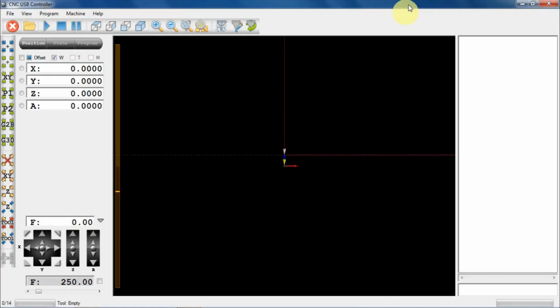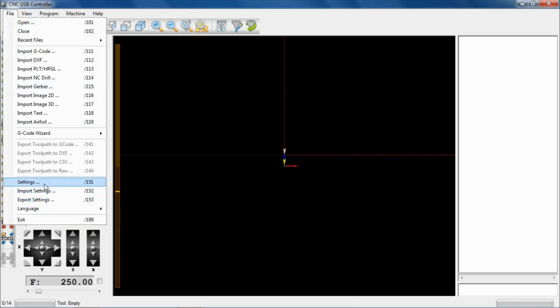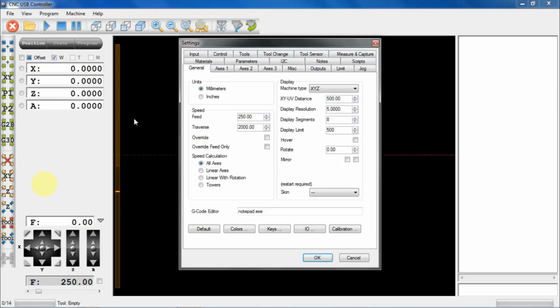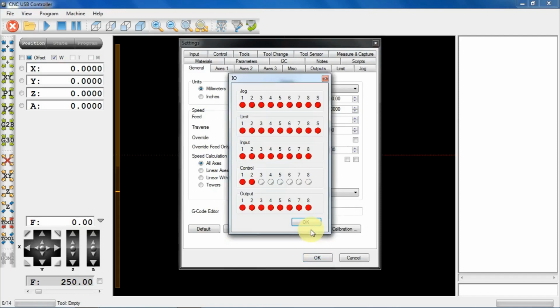Finding where this sensor's input actually is a bit of a challenge. In the interface, under file settings, it wasn't immediately obvious what needed to be done first, but I eventually worked out that this button here, I/O, gives us a real-time view of the state of each of the limit switches and the inputs and outputs. I don't believe this actually correlates in reality to what's on the controller board, but hopefully it will help us find out where that actuator is.